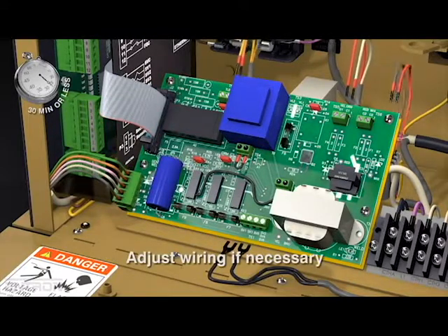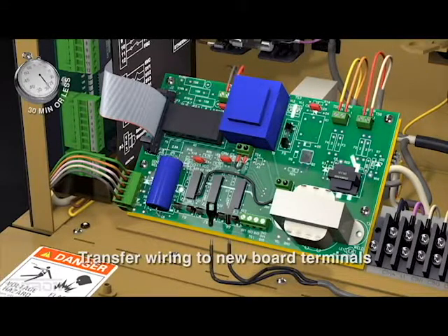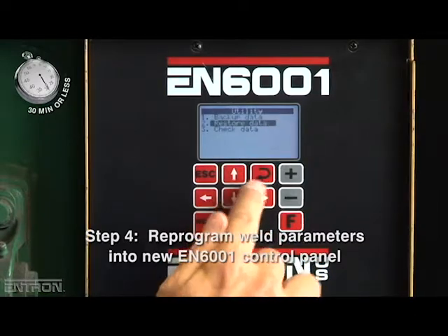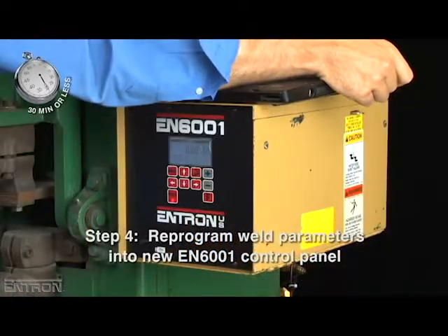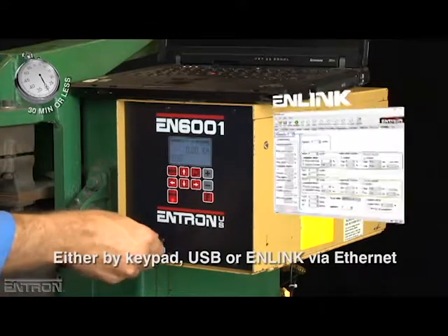The ribbon is connected to the new timer plate and circuit board, and the wiring, adjusted if necessary, is transferred to the new power circuit board's terminals. The last step is to reprogram the weld parameters into the new EN6001 control panel using the keypad, USB, or ENLINK via Ethernet.